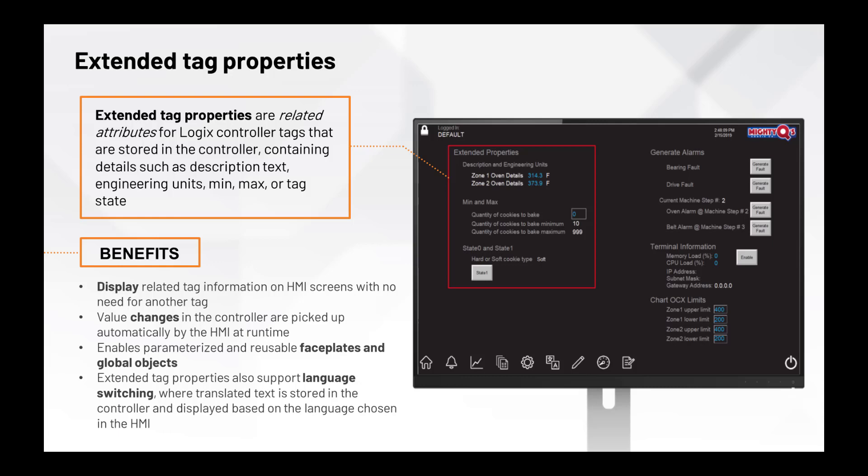The benefits of using Extended Tag Properties are that no additional HMI or controller tags are needed to display or manage these values. For example, to show a min-max value for a tag, you can simply access those properties. Min-max values are pulled directly from the controller and displayed in the HMI. Extended Tag Properties utilize on-change based communications, which means that data is only sent to the HMI on a change to minimize the communication load versus a normal tag that is continuously being polled. This powerful capability also increases application development productivity by enabling more efficient use of parameterized reusable faceplates and global objects. Extended Tag Properties support runtime language switching, where translated text is stored in the controller and displayed based on the language chosen in the HMI.